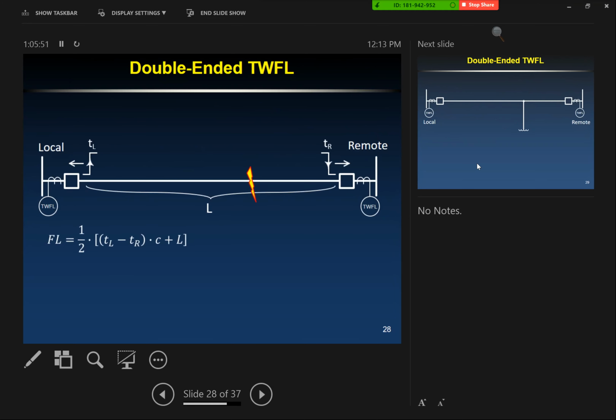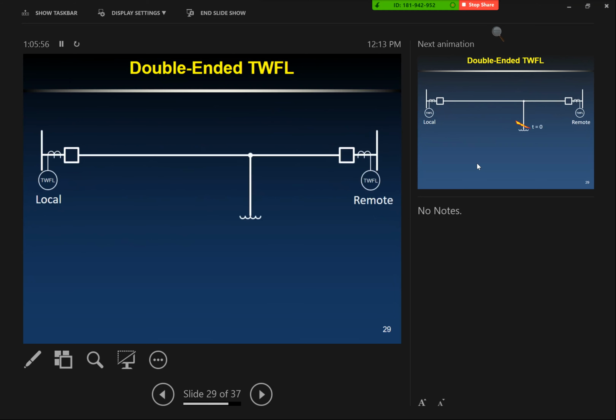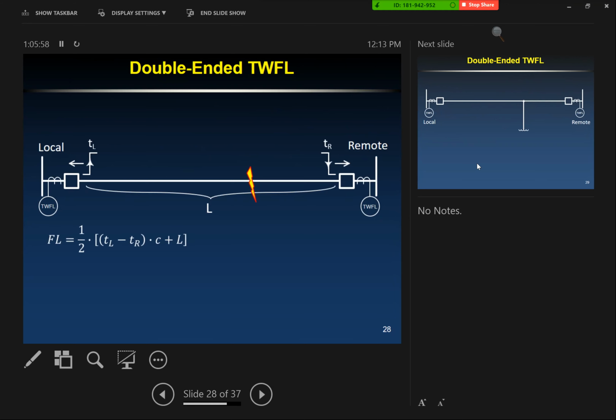And so that's going to spit out 5.2 miles, and you're done. And so the relays actually just calculate this. If they're connected through comms, they communicate that information to each other, and they report this number. If they weren't connected through comms, you could just pull up the relay event files, the header files. It shows this arrival time at both ends. Plug it into that simple formula, walk away, and you're done. C is the propagation velocity. So yeah, I should have put CR times C actually. So this would be your actual miles per second adjusted by that factor.